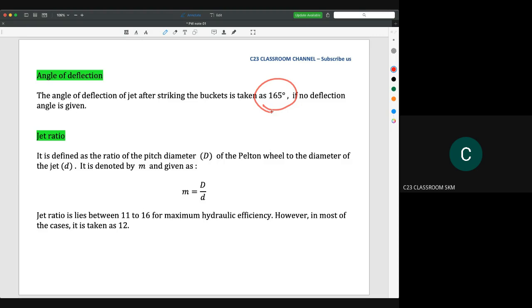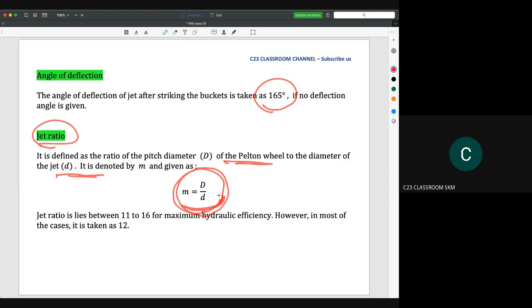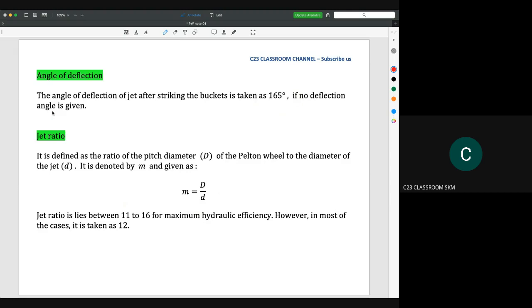The jet ratio is defined as the ratio of the pitch diameter of the Pelton wheel to the diameter of the jet. It is denoted by M and given as M = D/d. This is used to determine the optimum size of the nozzle relative to the wheel — if the nozzle is too big and the Pelton wheel diameter is too small, energy is wasted. For maximum hydraulic efficiency, the ratio M is 11 to 16, and the most common value is 12.